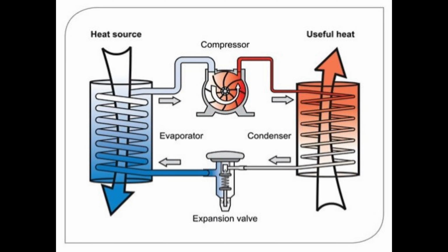Heat pumps work like refrigerators inside out. They use a refrigerant as an intermediate fluid to absorb heat where it vaporizes in the evaporator, and then to release heat where the refrigerant condenses in the condenser.